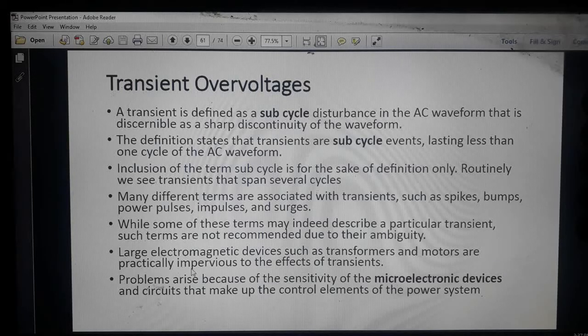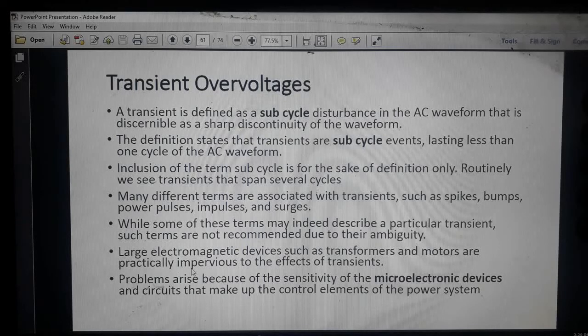The problem arises because of the sensitivity of the microelectronic devices and circuits that make up the control elements of a power system. The effect of transient over voltage may be on the microelectronic devices and circuits that make up the control elements which control the power system. That means if we are talking about the problem of transient over voltage, it may affect the sensors used in our transmission system, which may not operate properly due to the transient over voltage. This is the effect of the transient over voltage on our power system control elements.